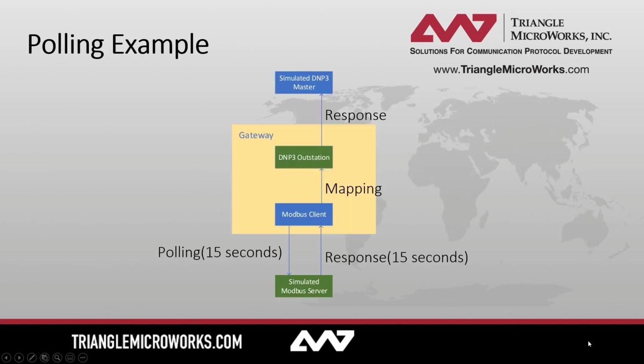This is the first example we're going to build up, and this is going to be with polling. We're going to have a control center with a DNP3 master, and our downstream device is going to be a Modbus server. Inside the gateway, what we need to build is a Modbus client in order to connect up to this server. We're going to execute polling in order to pull the values across, and we'll do that every 15 seconds, so we'll hopefully see a response about every 15 seconds. From there, we'll have the information inside of our client.